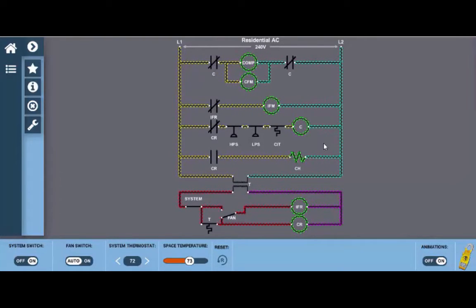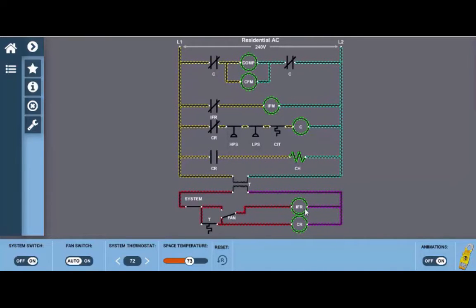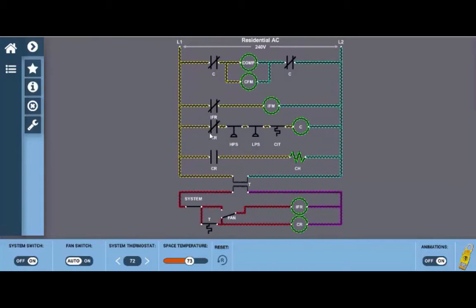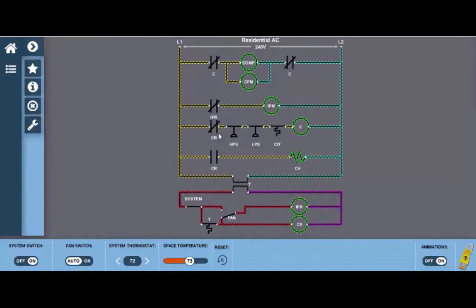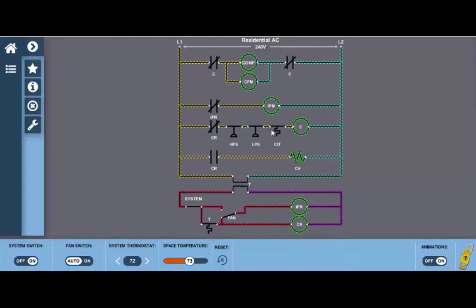Some manufacturers choose to leave the crankcase heater on all the time so as not to rely on a simple relay for protection. Now going back to CR if we look here we have the normally open contacts which now close. This allows current flow through those contacts and through the three safety switches: the high pressure switch, the low pressure switch, and the compressor internal thermostat to the contactor coil.